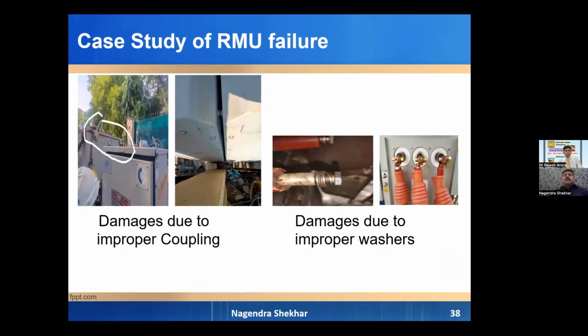On the left side, the coupling is not proper. There is a gap between the coupling of these two RMUs. And on the other side, you can see that spring washers are not used properly, resulting in current density and heating of termination, resulting in failures.